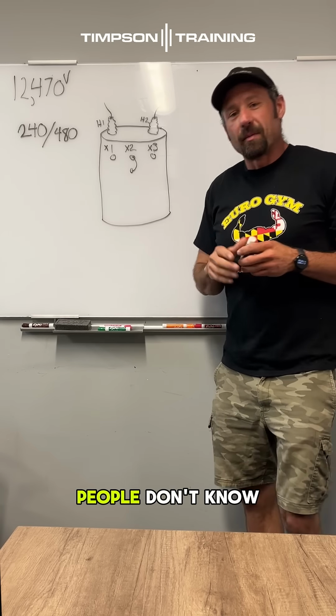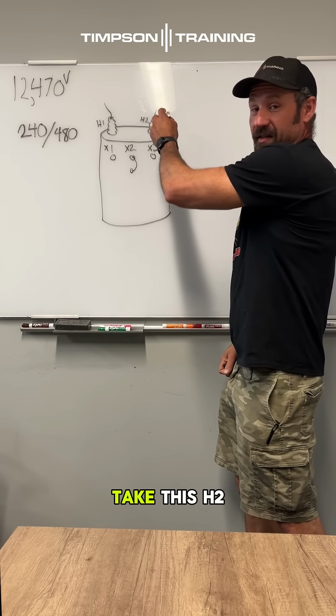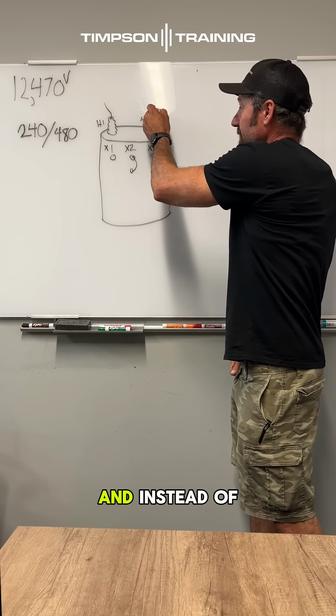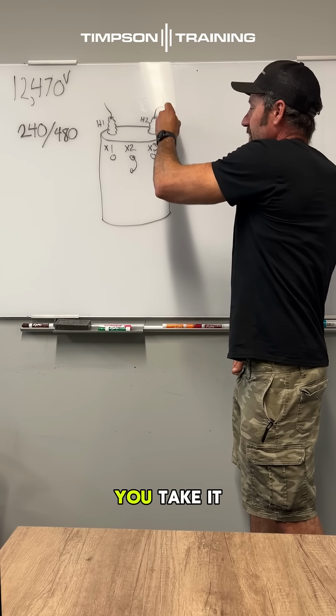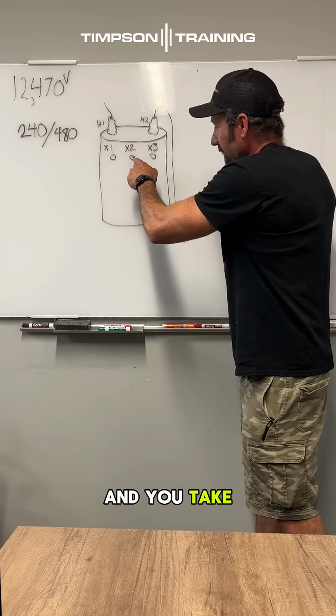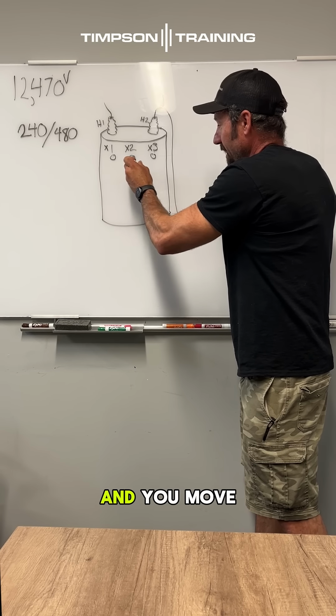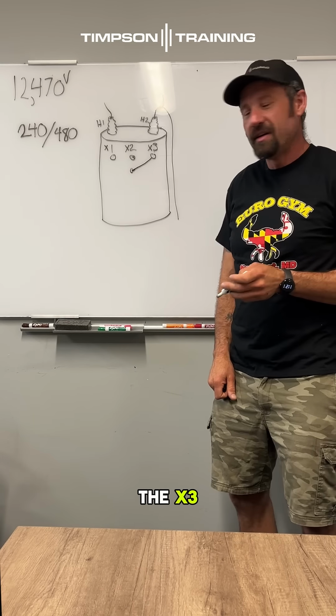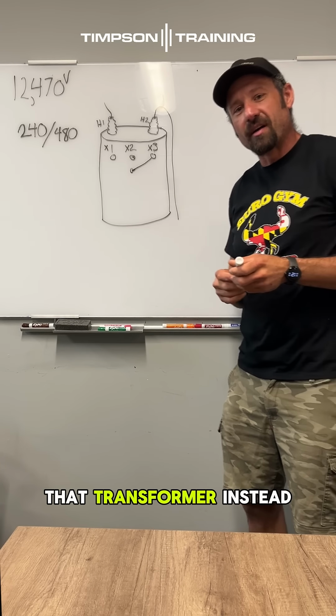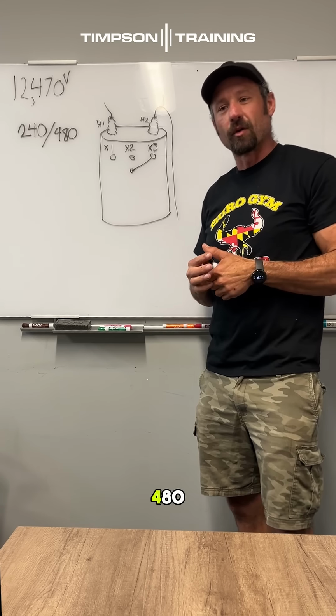But something a lot of people don't know: if you take this H2 on this transformer, and instead of taking it to a phase, you take it down to the neutral, and you move this ground strap over to the X3, you get 277 out of that transformer instead of 240/480.